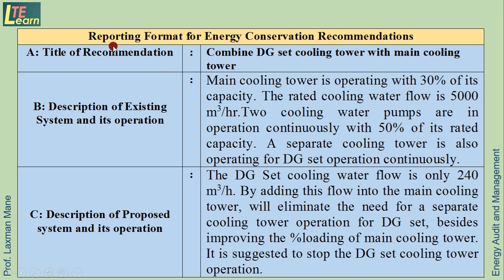Now we will discuss one sample reporting format for energy conservation recommendations. After the energy audit, what recommendations are given, that we will study from the case study. Here is the title of the recommendation: combine DG set cooling tower with main cooling tower. Actually, the main cooling tower and DG set cooling tower are operated separately. So the recommendation given here is to operate these two combinedly.